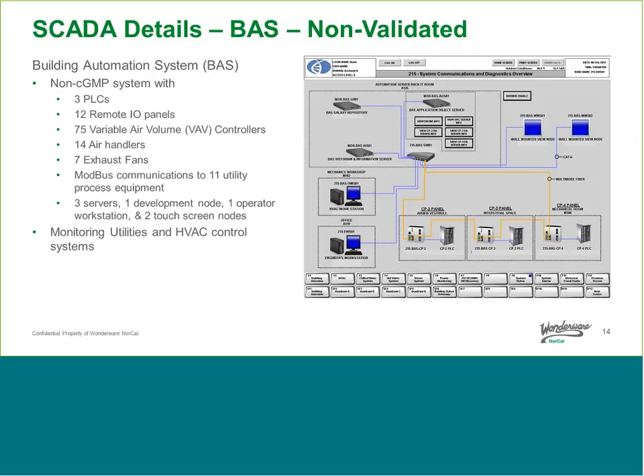And here I've broken out some of the points that are incorporated into the SCADA system. It pulled together 3 balance of plant PLCs. It had 12 remote I/O panels. There were 75 variable air volume, or VAV, digital controllers out in the field that were integrated over a proprietary protocol that we needed to integrate into Wonderware. It had 14 air handlers, 7 exhaust fans, and Modbus communications out to 11 utility process equipment. Those process equipment for the utility system included 3 plant chillers, 3 process chillers, 3 cooling towers, 2 hot water boilers, 2 steam boilers, and 2 heat exchangers, including the ability to move to free cooling.